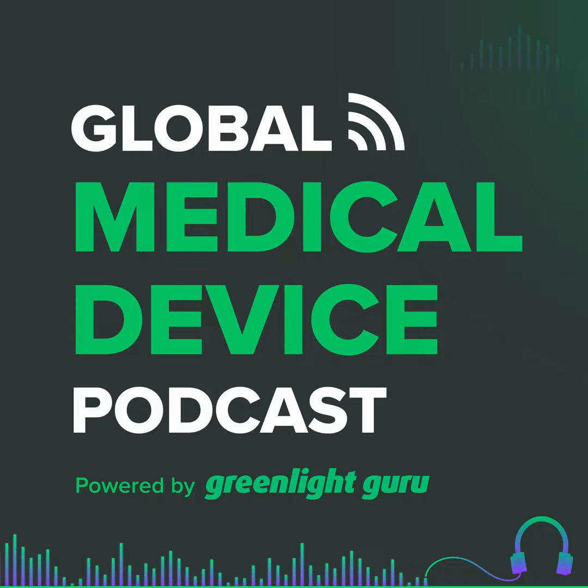But coming back to the original question, whether or not we need FDA permission to begin a clinical trial has to do with the risk of the device. And I've done podcasts with Greenlight before about the different systems for risk. Just as a recap, we have here in the United States three different independent but also interdependent systems that we handle risk with. One is the classification system, class 1, class 2, class 3. That system is what most people are familiar with.